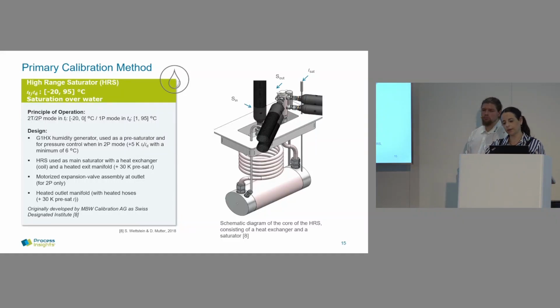Okay, so in the hot side, we have what we call a high range saturator. This time it's a 2 temperature, 2 pressure, or 1 pressure, depending on the dew and frost range. So if you are going frost, -20 up to 0, we are operating in 2 pressure, and up from 1 to 95 is 1 pressure.